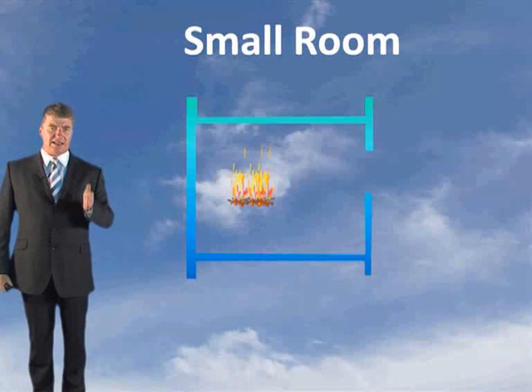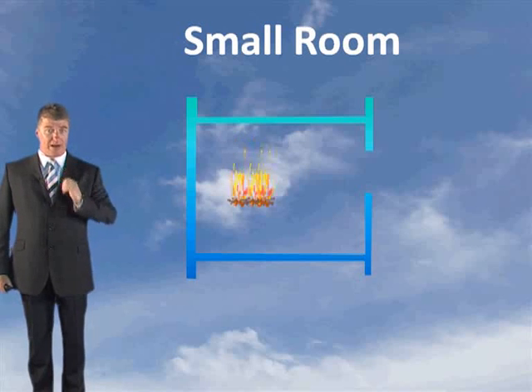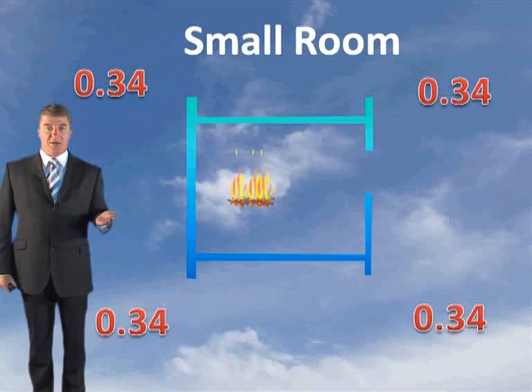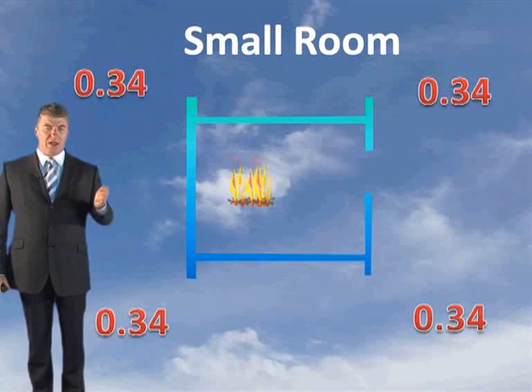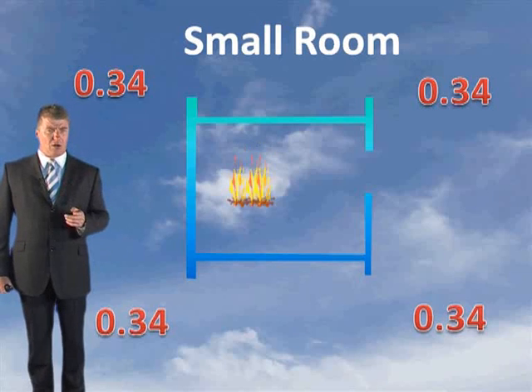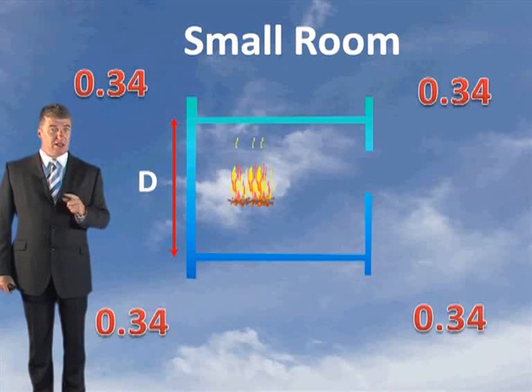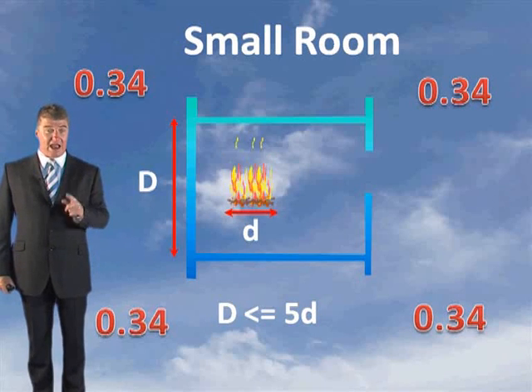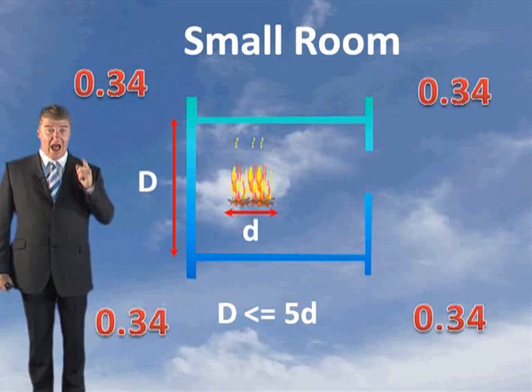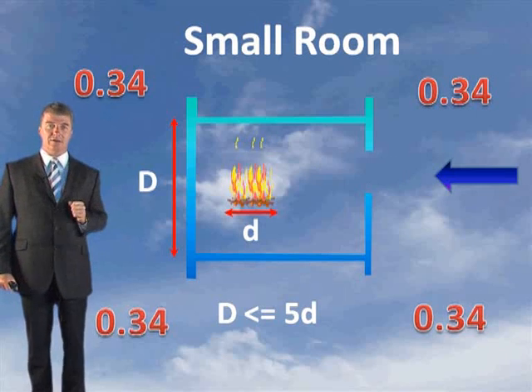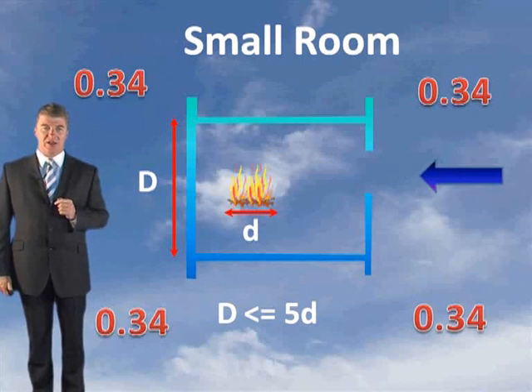If it's classified as a small room, you use 0.34 as your coefficient. A room is considered small when the maximum room dimension is less than or equal to 5 times the diameter of the design fire, and air can only come in from one direction. In this case we're not using 0.34 because air can come in from more than one entrance.